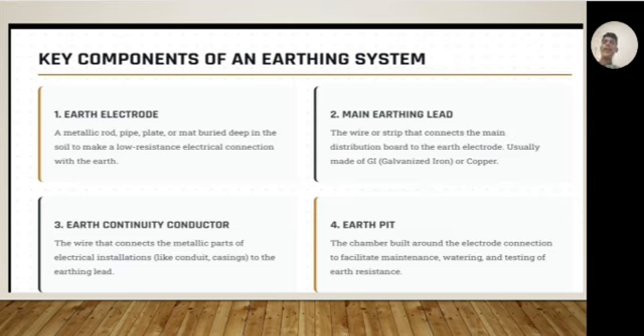Second point, main earthing lead. The wire or strip that connects the main distribution board to the earth electrode, usually made of GI. GI means galvanized iron, or copper. Third point, earth continuity conductor. The wire that connects the metallic parts of electrical installations, like conduit casing, to the earthing lead. Fourth point, earthing pit. The chamber built around the electrode connection. To facilitate maintenance, watering and testing of earth resistance.